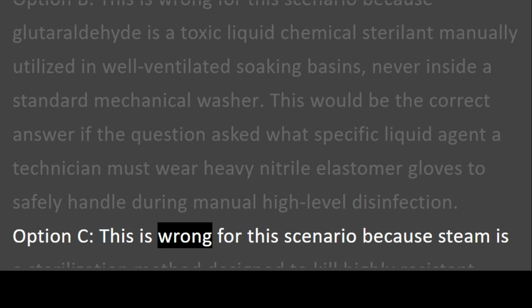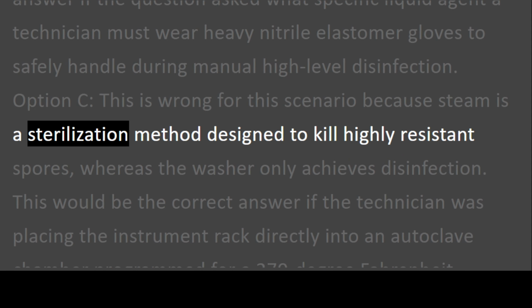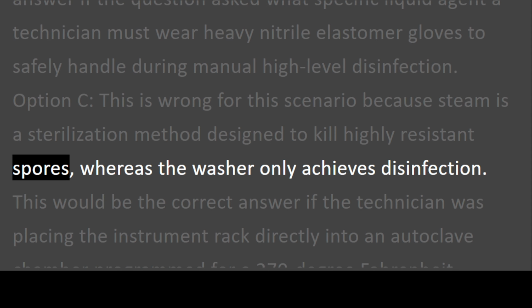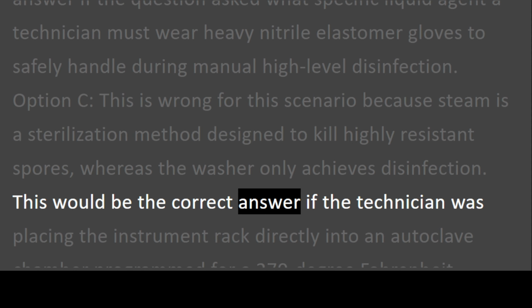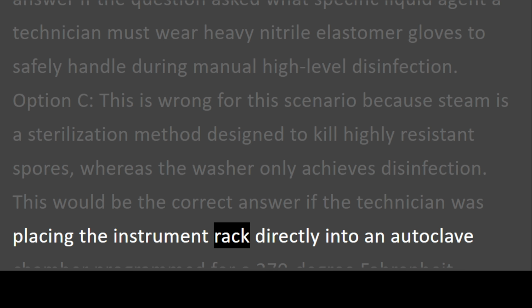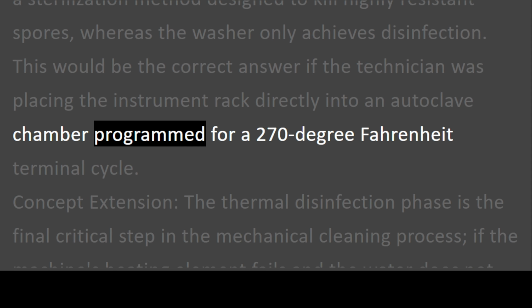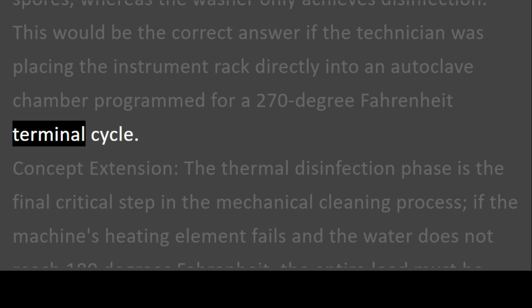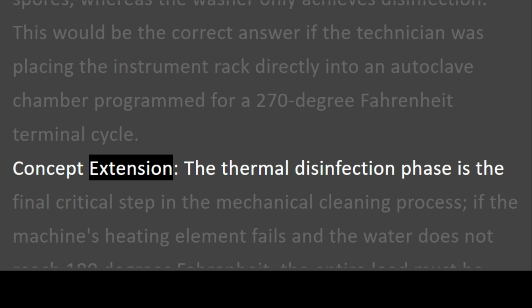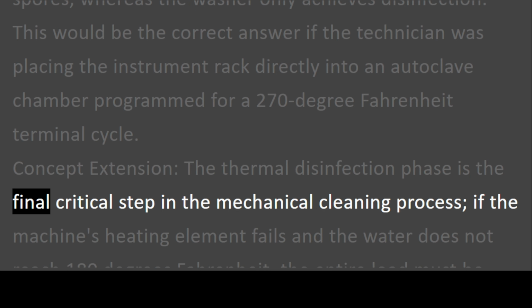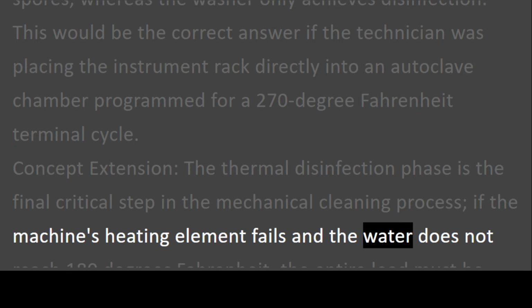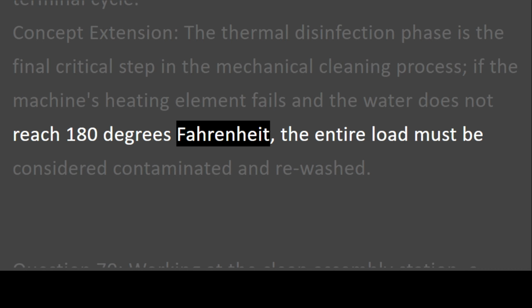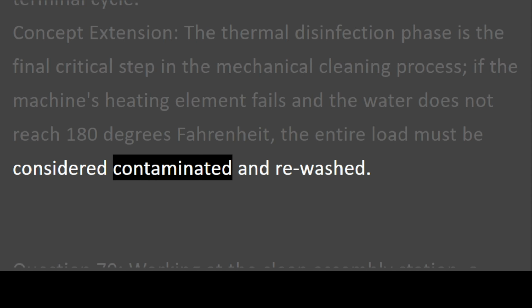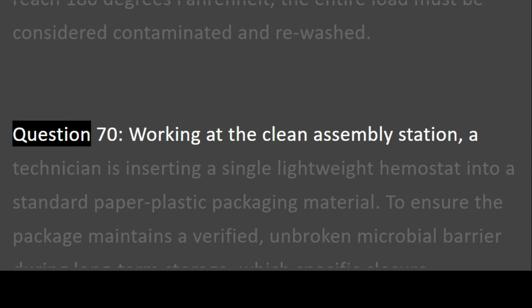Option C. This is wrong for this scenario because steam is a sterilization method designed to kill highly resistant spores, whereas the washer only achieves disinfection. This would be the correct answer if the technician was placing the instrument rack directly into an autoclave chamber programmed for a 270 Fahrenheit terminal cycle. Concept extension. The thermal disinfection phase is the final critical step in the mechanical cleaning process. If the machine's heating element fails and the water does not reach 180 Fahrenheit, the entire load must be considered contaminated and re-washed. Question 70.